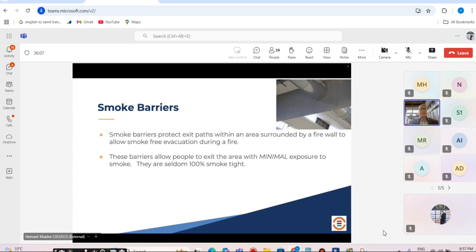So how these barriers are protected as part of compartmentation could be horizontal, vertical. Again, there are unprotected openings that exist in the building through pipes, cables, or ducts, which have to be sealed with fire sealant materials. There are glass facade openings. There are various other unprotected openings through your industrial operations or utilities areas. Those have to be sealed so that your openings don't become a passage for smoke movement.